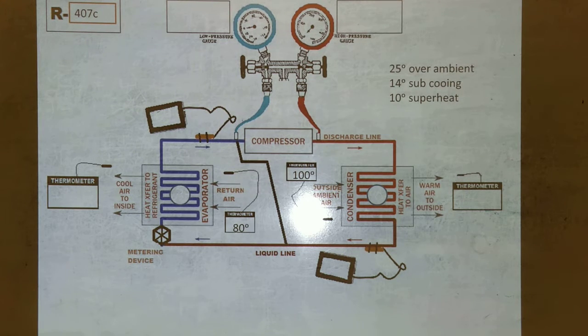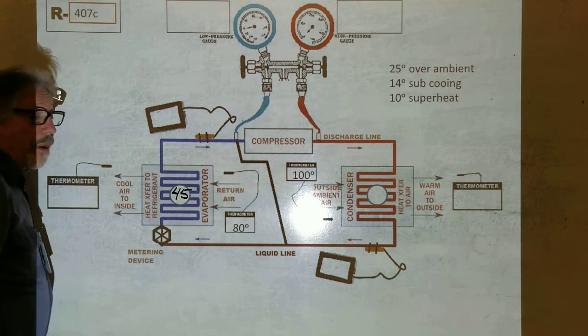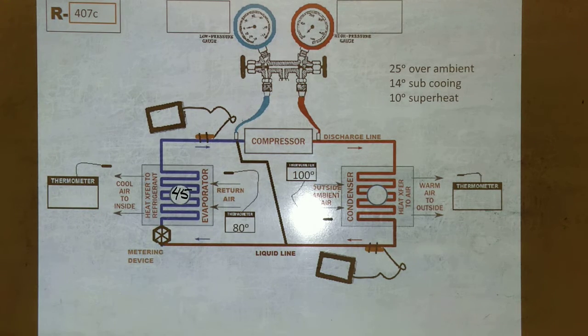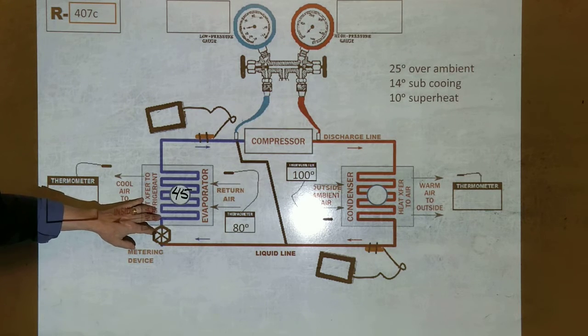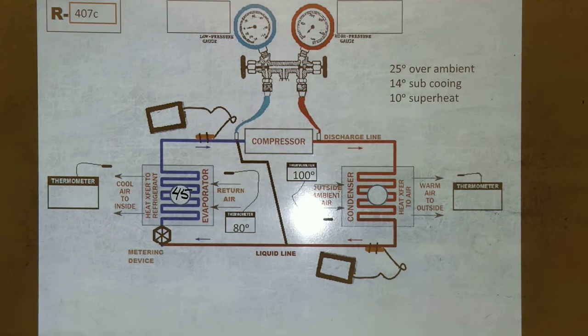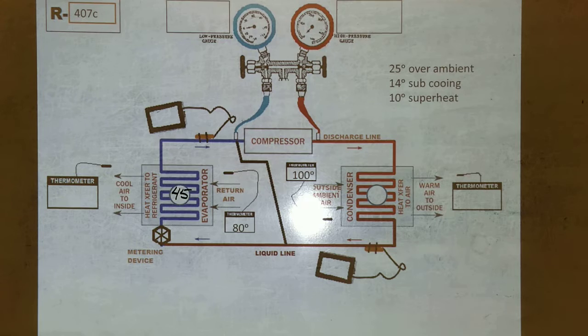The temperature difference should be 45. How'd you get 45? Subtract. Just think of it this way, this will help you remember. That evaporator in the air duct, that's in the airstream, has to be colder than the inside of the house in order for the temperature to drop, right? If it was hotter than 80 degrees, it'd be a heater, right?